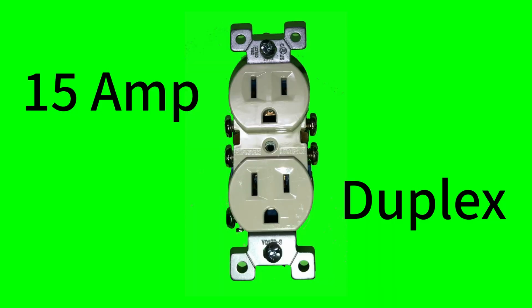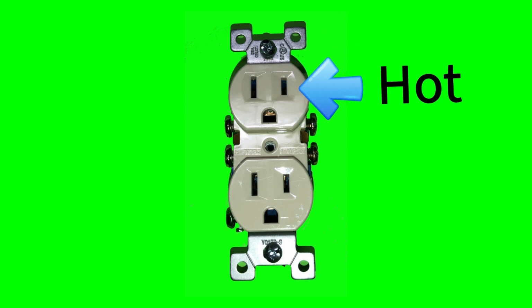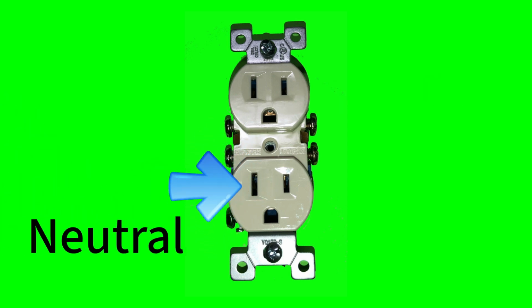Here's a bit of valuable information before we get started with the testing. This is a 15 amp standard duplex outlet. Look closely at the openings in the outlet. There are 3 per outlet. The smaller straight opening is the hot connection, also called the line side. This opening is connected to a fuse or circuit breaker. The larger of the slotted openings is the neutral connection, which does not go through a fuse or circuit breaker. The larger slot ensures that an ungrounded cord is plugged into the outlet properly. In other words, there is a right way and a wrong way to plug a cord into the receptacle.